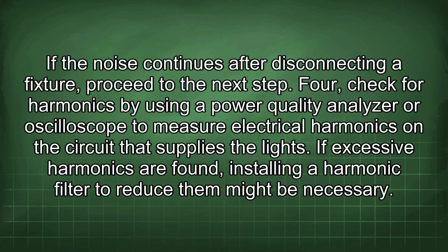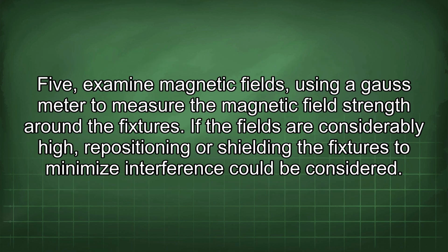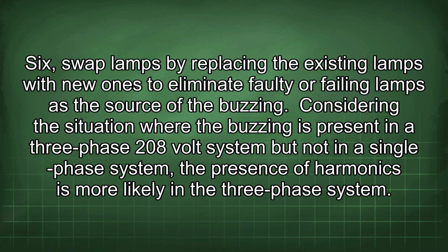4. Check for harmonics by using a power quality analyzer or oscilloscope to measure electrical harmonics on the circuit that supplies the lights. If excessive harmonics are found, installing a harmonic filter to reduce them might be necessary. 5. Examine magnetic fields, using a Gauss meter to measure the magnetic field strength around the fixtures. If the fields are considerably high, repositioning or shielding the fixtures to minimize interference could be considered. 6.